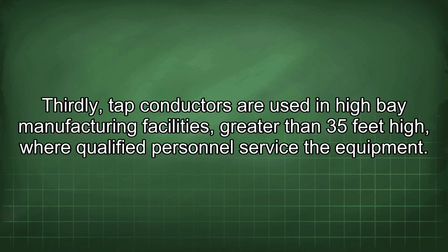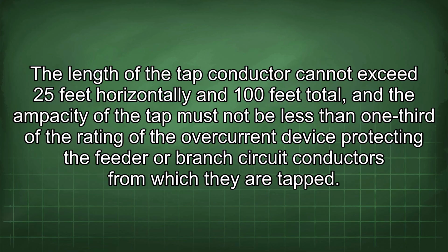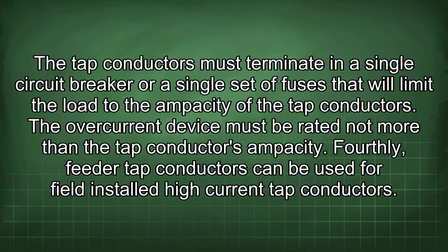Thirdly, tap conductors are used in high bay manufacturing facilities greater than 35 feet high, where qualified personnel service the equipment. The length of the tap conductor cannot exceed 25 feet horizontally and 100 feet total, and the ampacity of the tap must not be less than 1/3 of the rating of the overcurrent device protecting the feeder or branch circuit conductors from which they are tapped. The tap conductors must terminate in a single circuit breaker or a single set of fuses that will limit the load to the ampacity of the tap conductors. The overcurrent device must be rated not more than the tap conductor's ampacity.